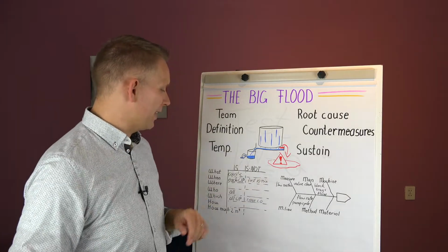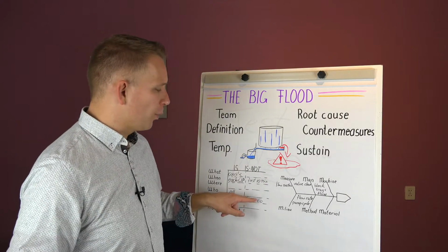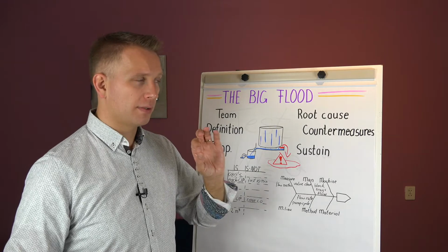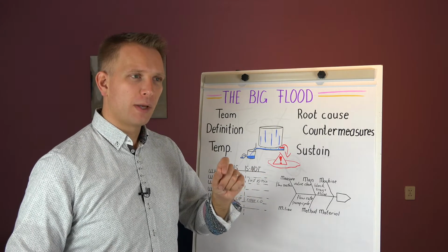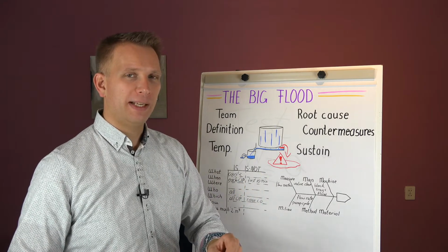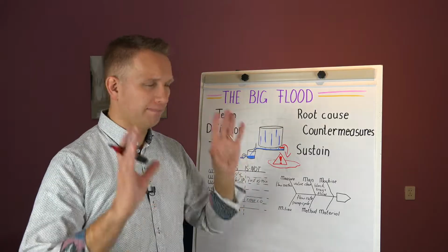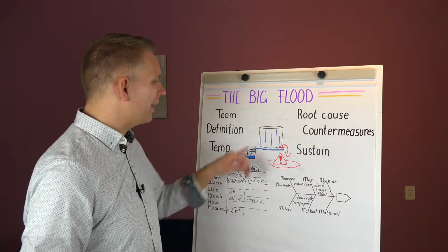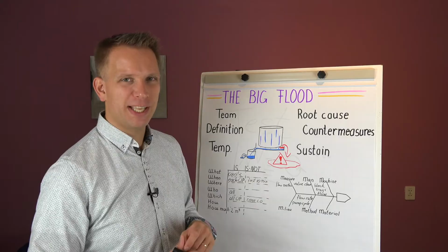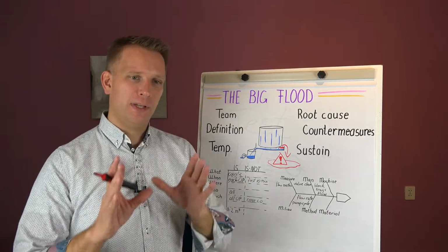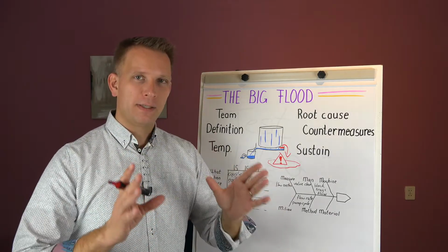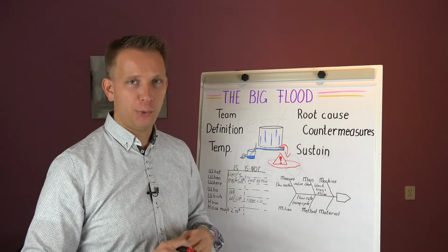So every cleaning basically has it, although when we do a changeover rinse, which is a quick system, we did not see the problem happening like that. But if you do a full cleaning, you get the problem. That might also be linked to the fact that we didn't really see it in the first 10 minutes, but about a minute after the start of the main cleaning phase, it would start to overflow.